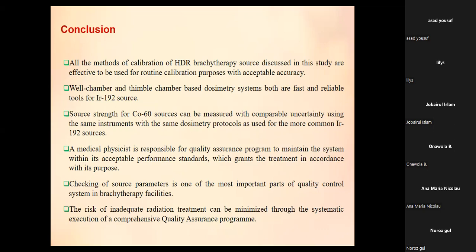A medical physicist is responsible for the quality assurance program, to maintain the system within its acceptable performance standard, which grants the treatment in accordance with the purpose. Checking the source parameters is one of the most important parts of the quality control system in brachytherapy facilities. The risk of inadequate radiation treatment can be minimized through the systematic execution of a comprehensive quality assurance program.